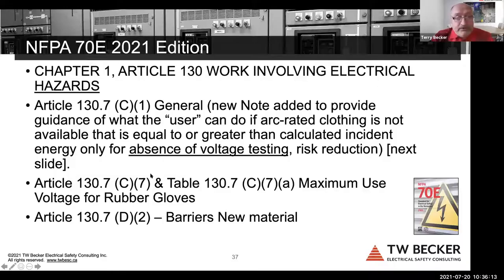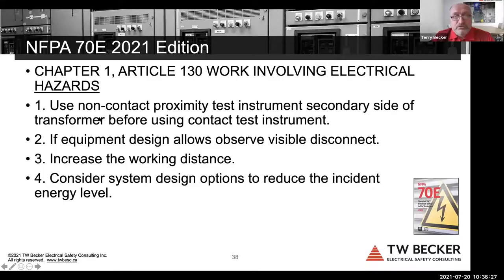Let's see, work involving electrical hazards, a new note added to provide guidance. This is where the incident energy is greater than available arc flash PPE, and it's only for absence of voltage testing that it lists some steps you can take to reduce risk: non-contact proximity tester, observe visible disconnect, increase the working distance, consider system design options. So unfortunately, item 4 would be a more proactive approach where the incident energy is greater than arc flash PPE available.